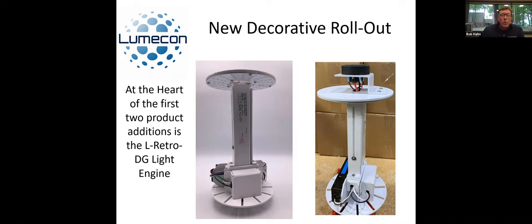It is built to withstand vibration, to live thermally inside of a globe, and to disperse the luminous output in a very uniform manner. As you can see on the slide, it has a universal mounting plate. We include a 40 kV surge suppression system. We have a programmable driver so we can move from 35 to 55 watts. And then we have a telescoping neck that can move up and down up to nine inches to fit into almost any size acorn or round globe. The LED array is set up in a full cutoff manner — once it's in the globe it's no longer full cutoff, but in itself it is.